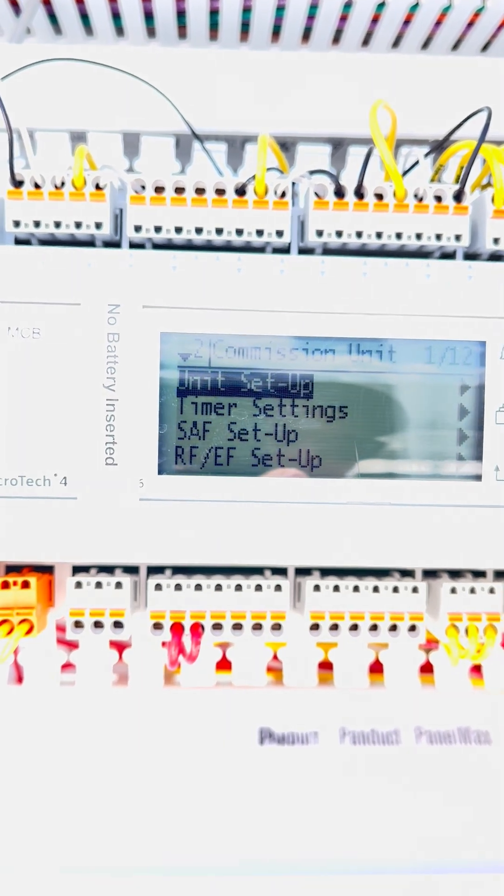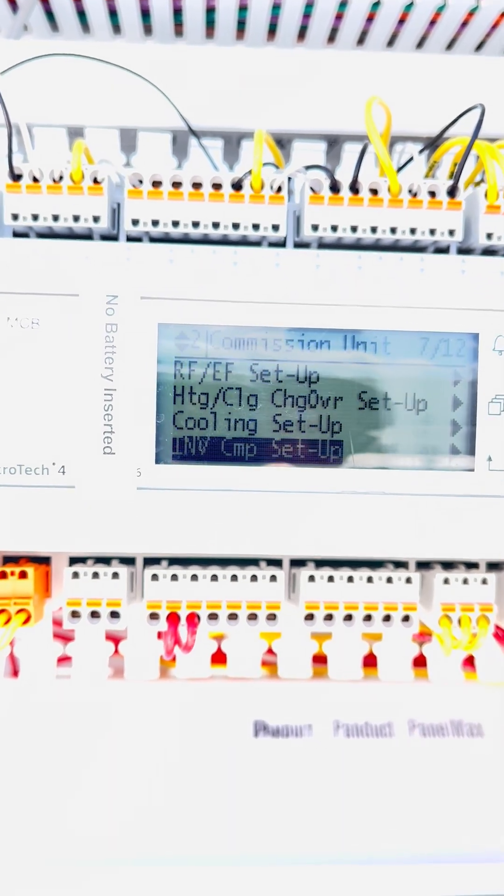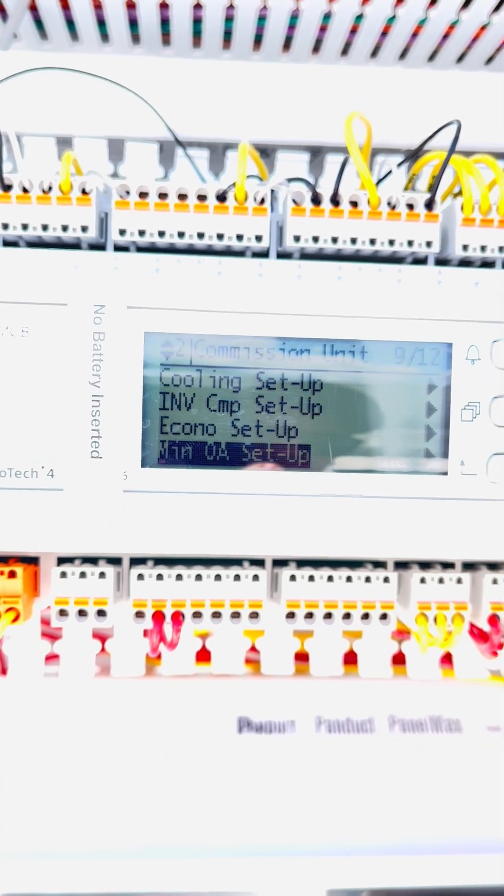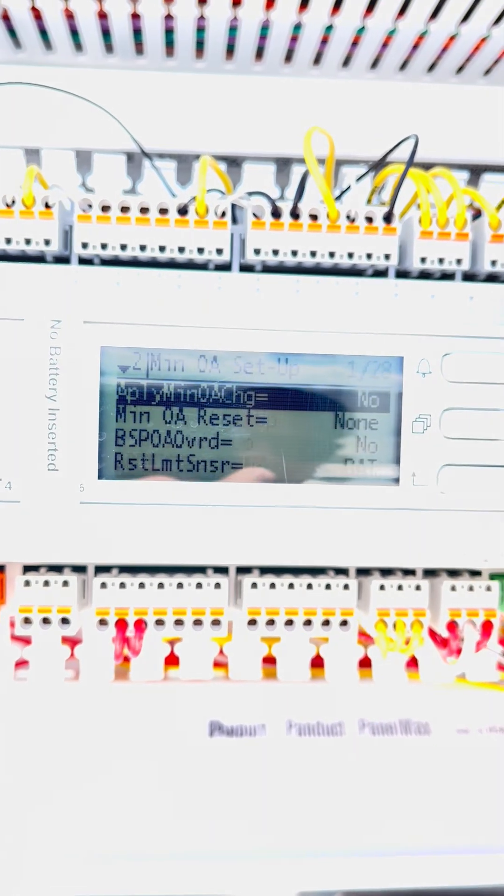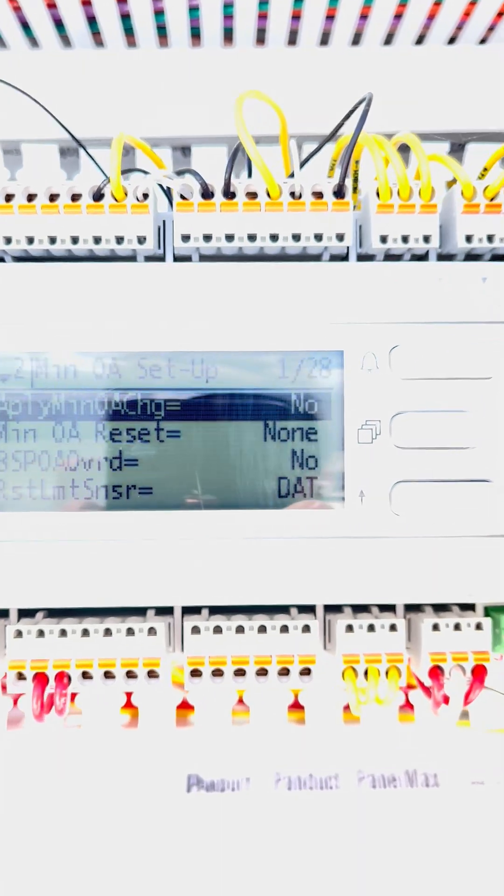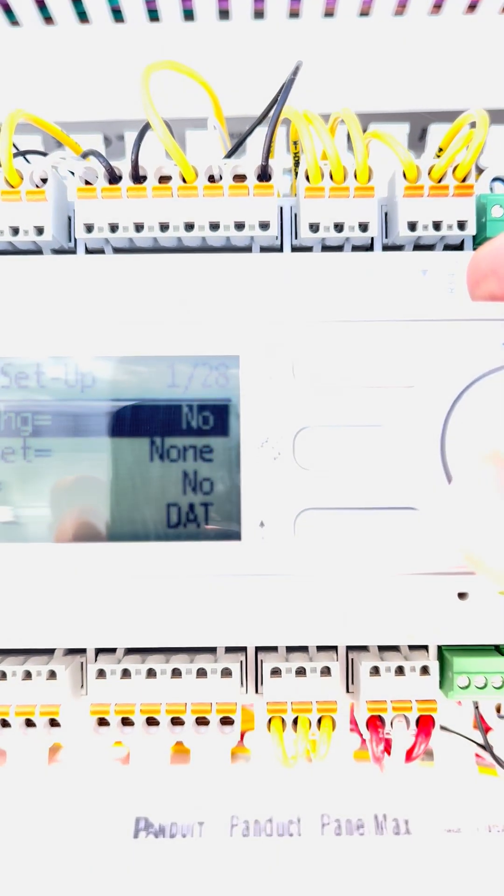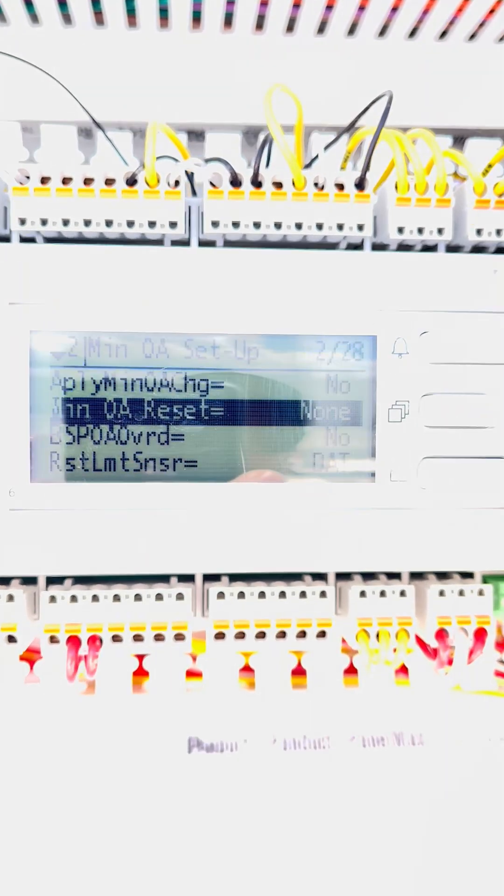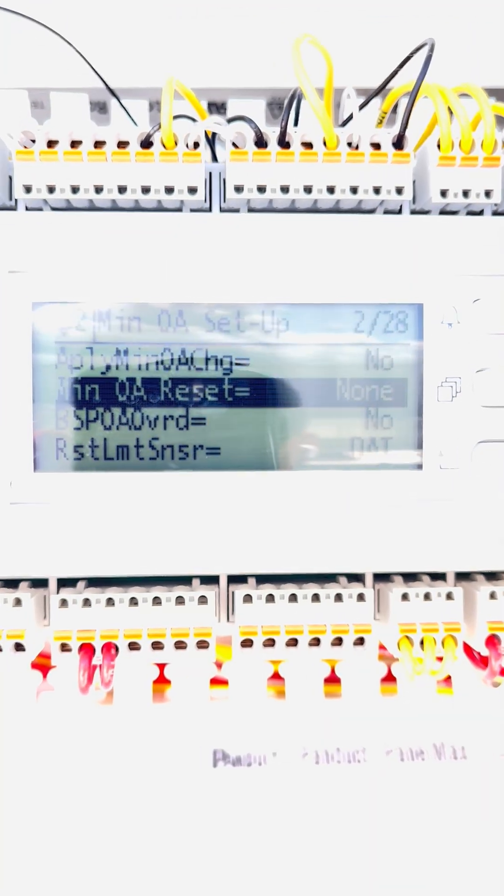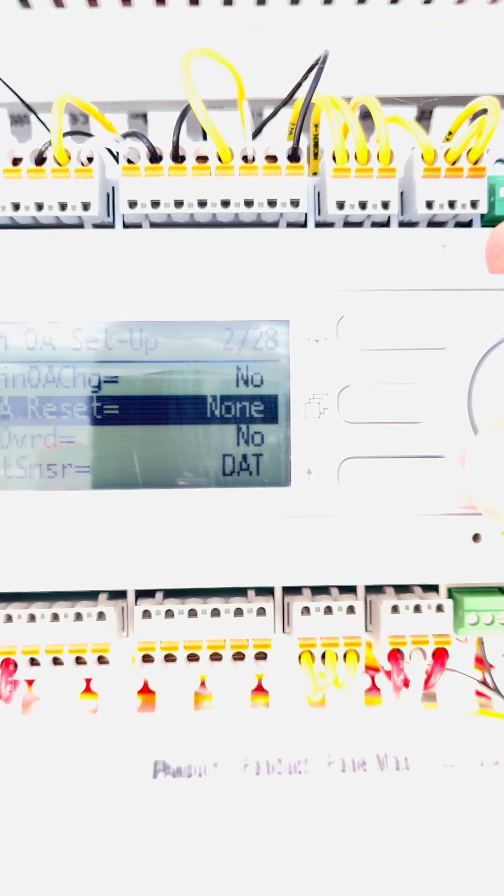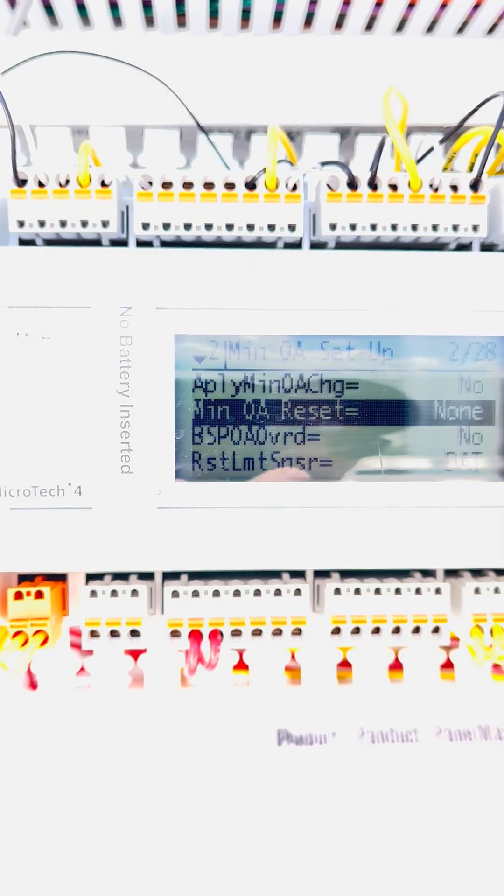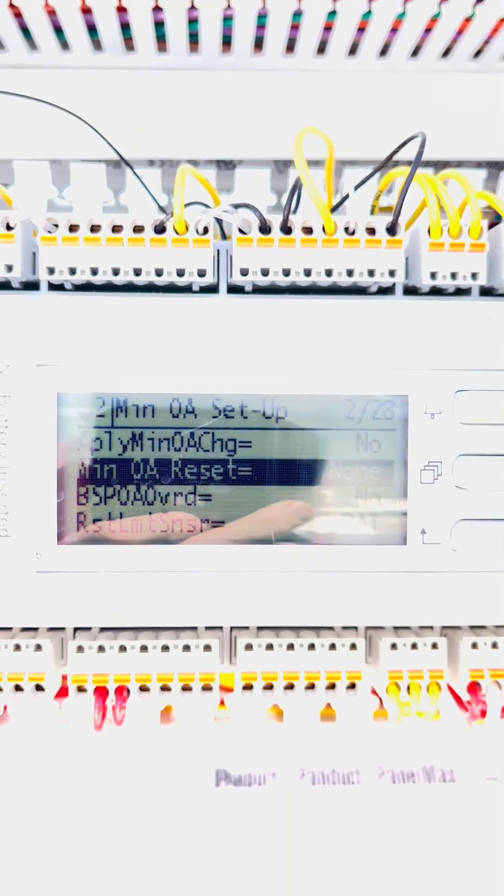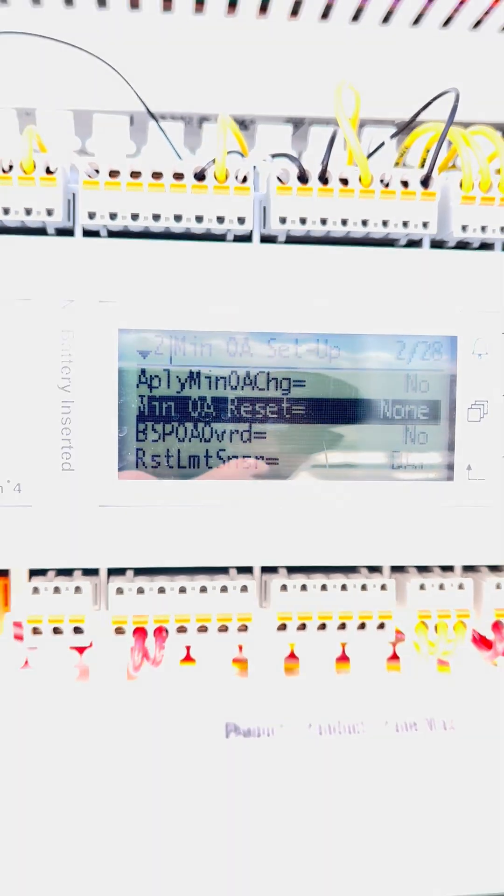Now, we have to go to commission unit, and in commission unit, we go down to the same thing, min outdoor air setup. Notice here that we have to save these settings at the top on that last setting to apply changes. Min outdoor air reset. If it's set to network, you have to set this to none. If you set it to network, network takes priority over the actual flow station.